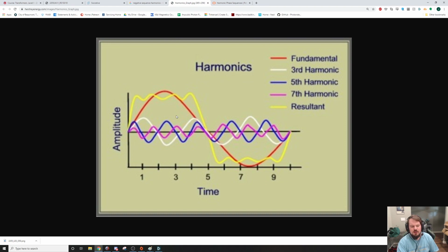There's a reason why we've been using the neutral wire, like sharing the neutral less and less. You can have 2 circuits sharing a neutral and they should cancel out. But if you do not have a pure sine wave, they won't cancel out efficiently. So whenever everything was incandescent lights, the powers of those 2 incandescent lights would cancel out on the neutral, if they were on different phases.